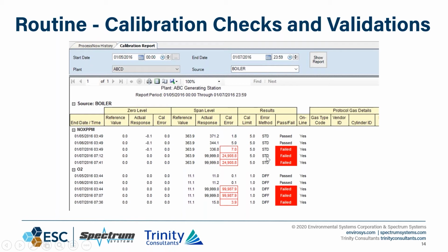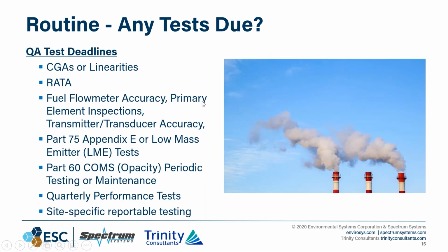And I would like to note that if you ever see 99,999 on your calibration error report, you should probably call your CEMS consultant or DAS provider immediately. Ooh, that's a trick question, isn't it? Does that mean there was a communication glitch? It could be, yeah. So I was looking at those numbers, and that right there is the trend for trending upwards towards your performance specs.